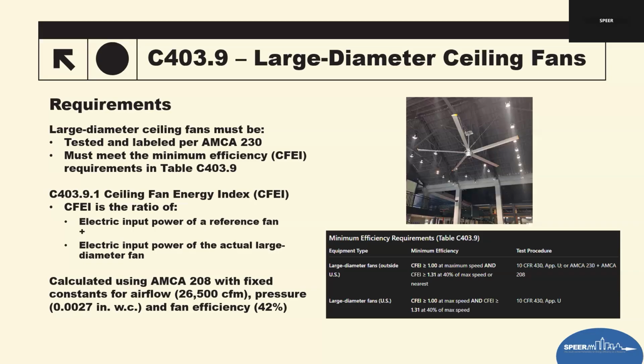And then, understanding CFEI, basically it is the ceiling fan efficiency index, a performance metric that compares the actual fan's power use to a reference fan using the standardized AMCA 208 calculations. Practical takeaways for plan reviewers: verify that submittals include test data using correct test procedures. Check that the CFEI values at both max speed and 40%, or relatively around the closest speed that you can get, if maybe it's 50%.